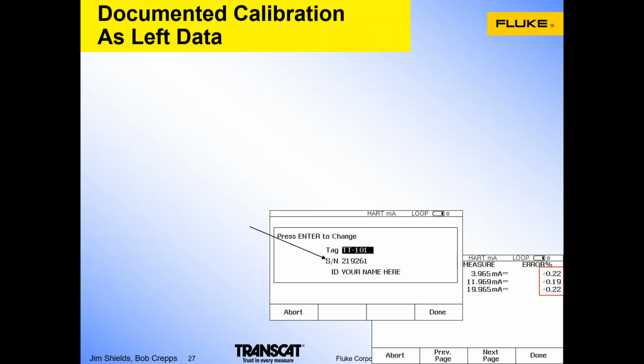So after the adjustment is performed, an as left needs to be taken. In the event that no adjustment was performed, the as found can be taken as the as left, and no as left test necessarily needs to be performed, because if the as found test determines that everything is in specification, you're essentially done with the task unless your organization indicates that you must perform a trim, even though the test was within tolerance.